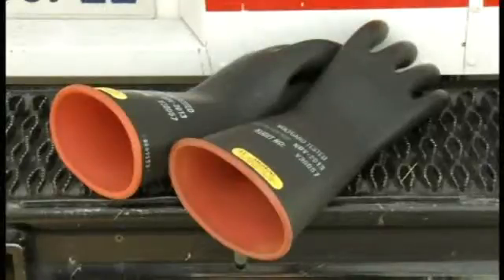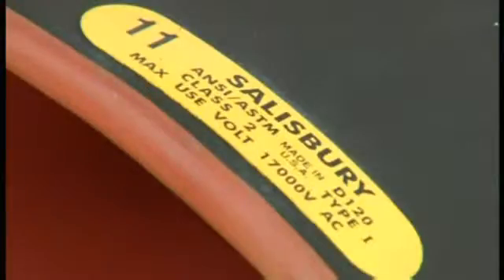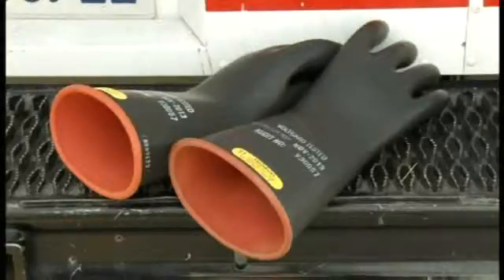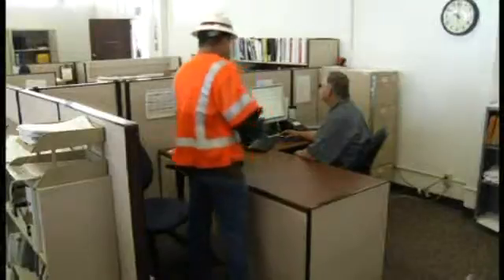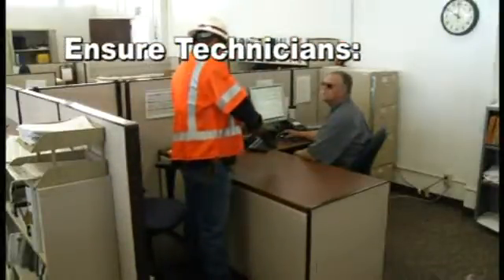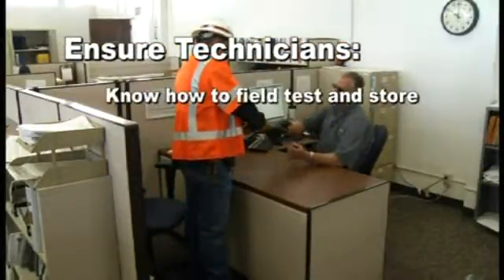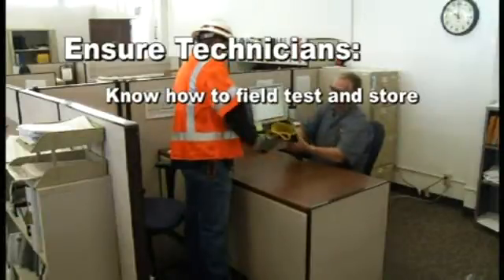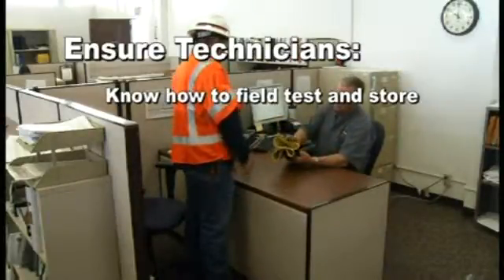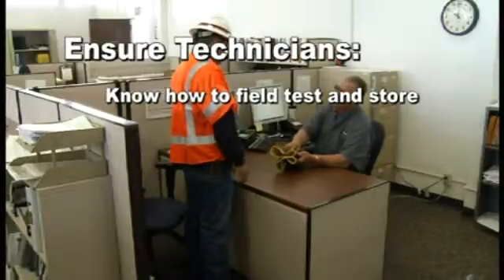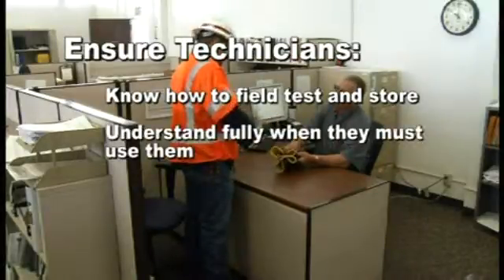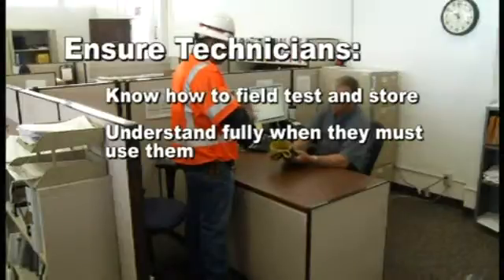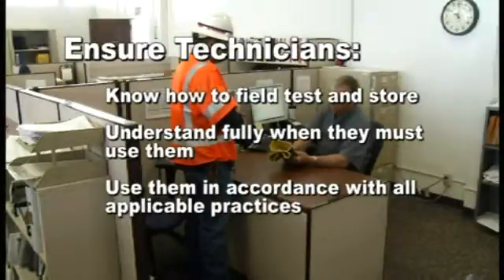All Verizon outside plant employees are issued Class II Type 1 insulating gloves. Each of these gloves has a date stamp stating when they need to be retested. Gloves can be used until the last day of the month and year stamped on the glove. As their supervisor, you must ensure that technicians know how to field test and store their gloves as described in the VZTV video, Insulating Gloves, Testing, Use, and Storage. Understand fully when they must use them. Use them in accordance with all applicable practices.